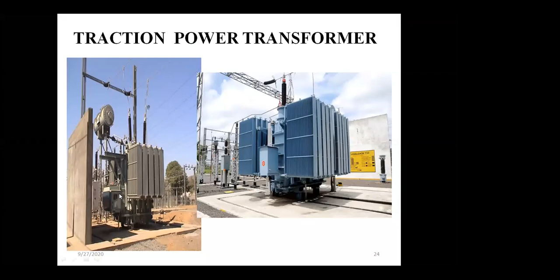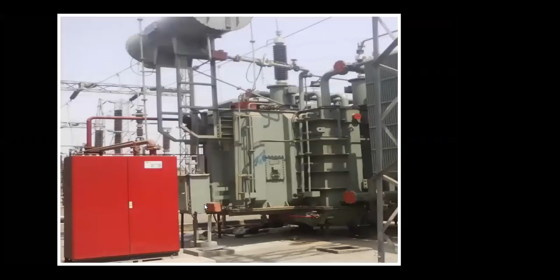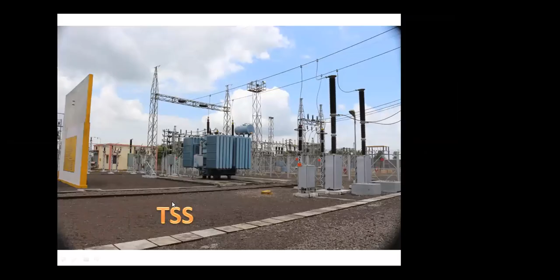This is a photograph of a traction transformer in two different views. Now this is a photograph of a 40 MVA traction transformer with automatic fire detection system. Indian Railway has introduced this automatic fire detection and fire quenching system for traction transformers. If anything goes wrong in this traction transformer, the whole automatic system takes care and the fire is extinguished automatically. Of course, we take all due care to avoid such untoward incidents. We will also see the precautions and everything in detail.